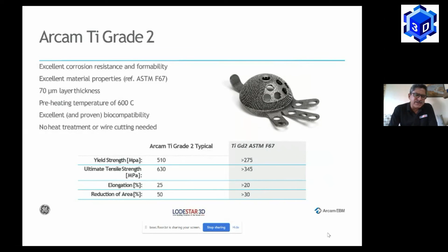This is another significant aspect of the machine or equipment, which is a key demand or requirement when it comes to orthopedic implant manufacturing. It's to find a system in which quality is monitored, checked and verified. So Arcam has a system which they call LayerQam, which helps to detect, layer by layer, mostly the relative density aspect of the build. That is to convey whether, during an entire build process, there has been any area where the expected melting process has not happened for any reason.